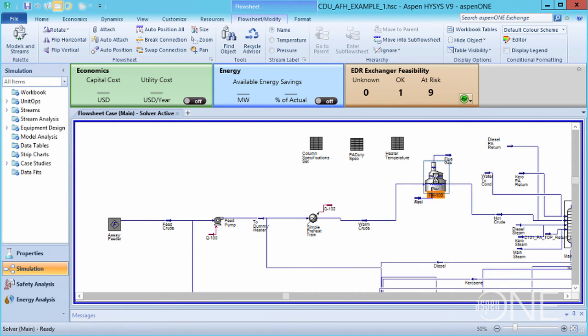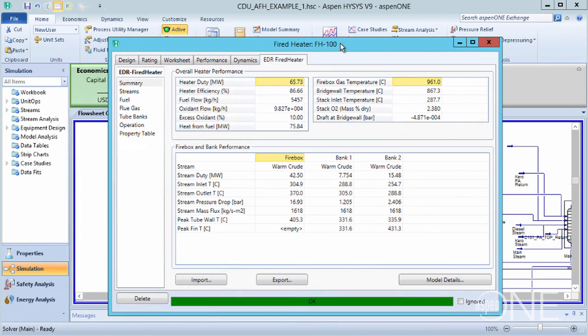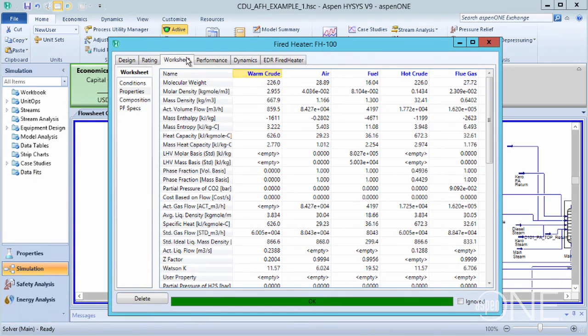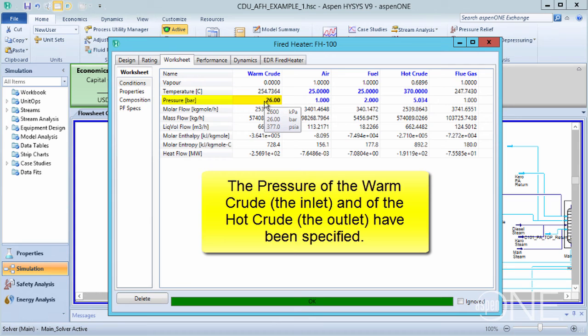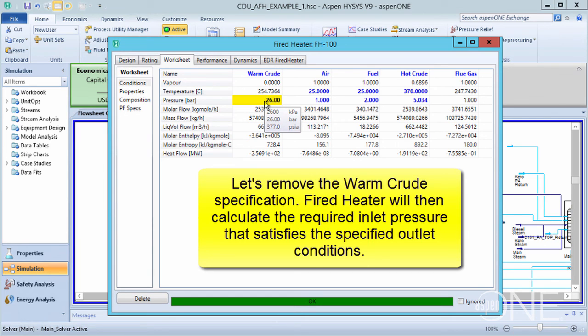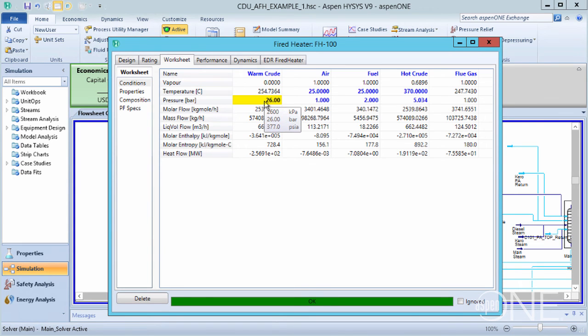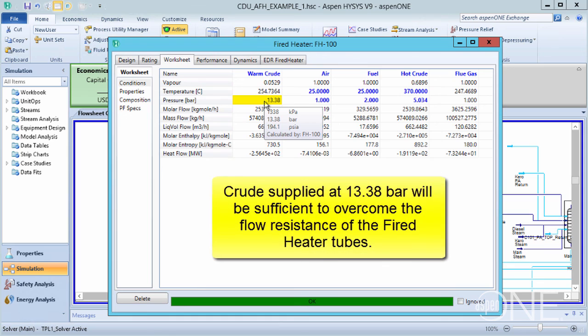Now let's open the fired heater model again and go to the worksheet tab. You may observe that the pressure of the warm crude, the inlet to the furnace, has been specified as well as the pressure of the outlet, the hot crude. Let's make better use of fired heater hydraulics. If we remove this specification, we will be using fired heater to calculate what inlet pressure is required in order to satisfy the requirements of the outlet condition of the heater. You should see that HYSYS converges quite quickly. If the crude is supplied at this pressure, 13.38 bar, it will be sufficient to overcome the flow resistance of the fired heater tubes.